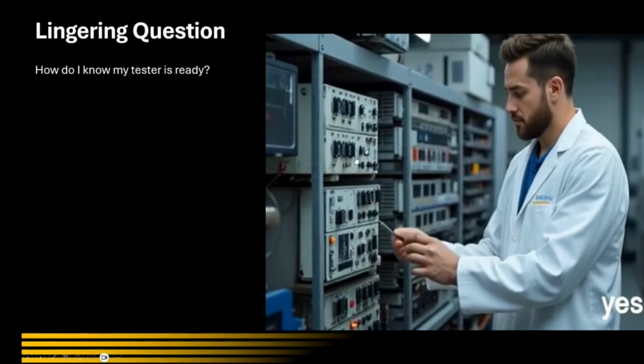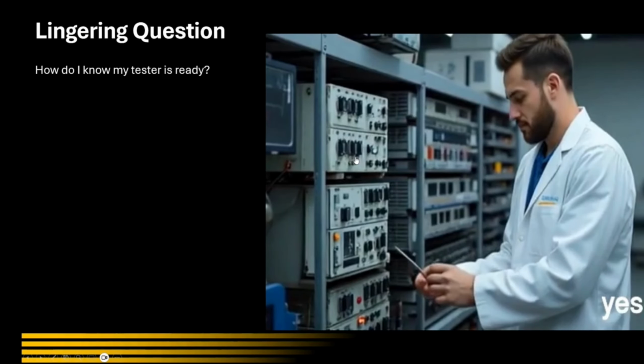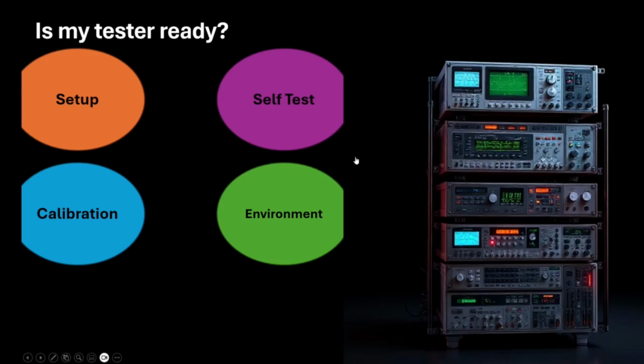So how do I know my tester is ready? I run the calibrations, but how do I know the calibration is done correctly? These are the few things that we normally make sure of before we run the test, like the tester setup. Sometimes we have to run a self-test on some of the instruments, making sure that they are still working fine. Then calibrations, especially when you have testers such as a network analyzer or a spectrum analyzer, just to make sure that the offset is done correctly. Amplifier, filter: you use the right product in the whole network of tests. And then you also make sure that the environment is constant, where your temperature is controlled to a certain degree and your humidity is controlled to a certain degree.